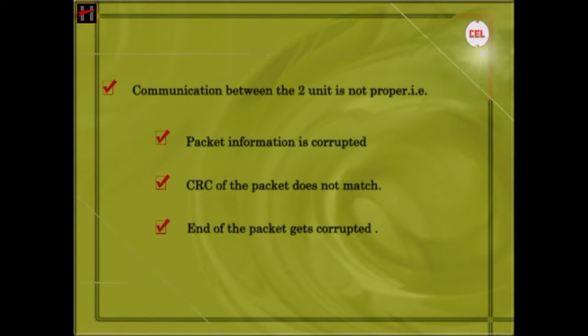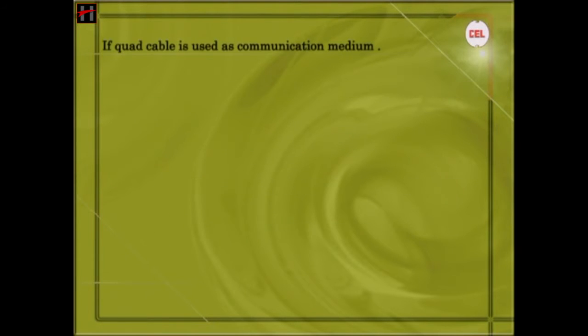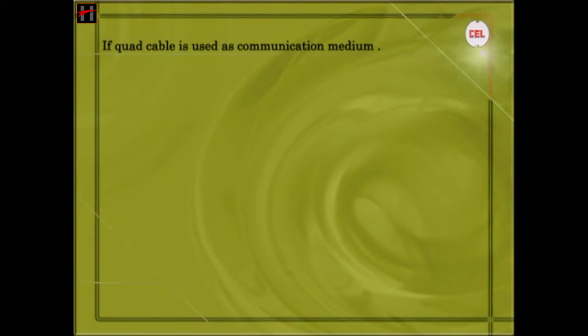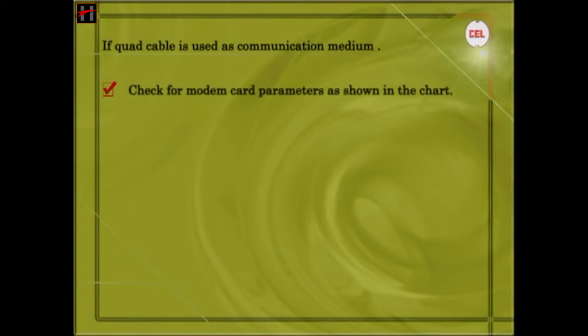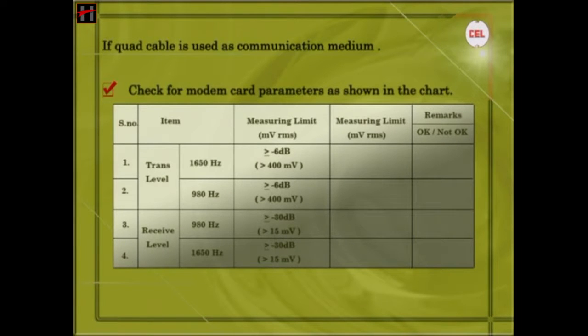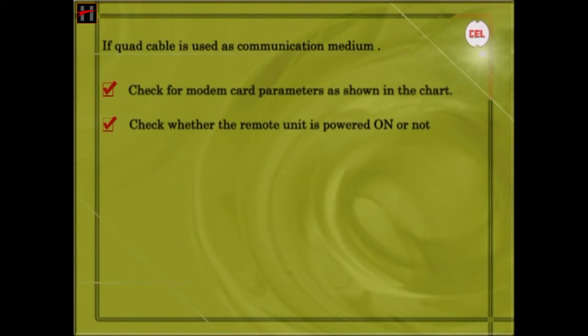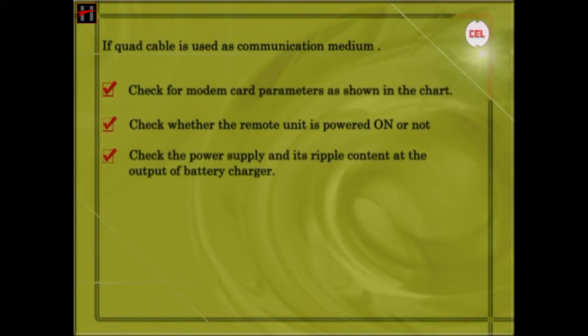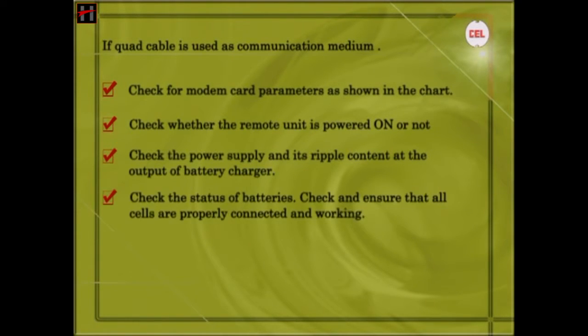If any of these errors occur in the system, carry out the following checks to rectify them. If quad cable is used as communication medium, check the modem card parameters as shown in the chart. Check whether the remote unit is powered on or not. Check the power supply and its ripple content at the output of the battery charger.